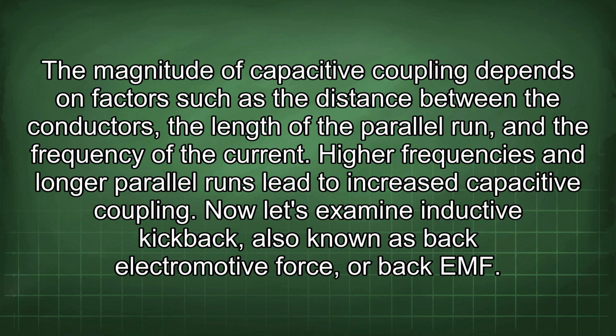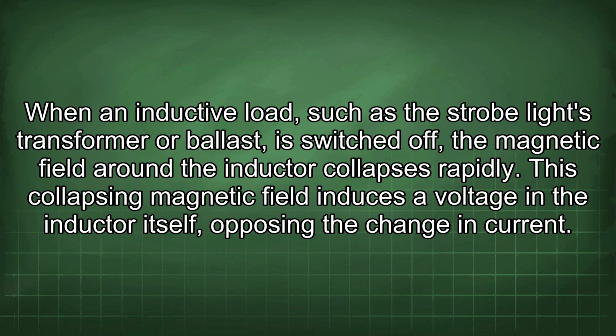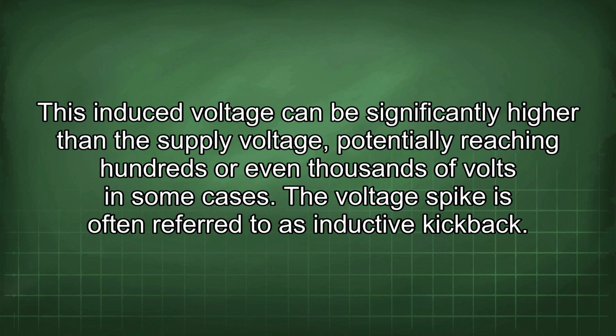Now let's examine inductive kickback, also known as back electromotive force or back EMF. When an inductive load, such as the strobe light's transformer or ballast, is switched off, the magnetic field around the inductor collapses rapidly. This collapsing magnetic field induces a voltage in the inductor itself, opposing the change in current. This induced voltage can be significantly higher than the supply voltage, potentially reaching hundreds or even thousands of volts in some cases. The voltage spike is often referred to as inductive kickback.